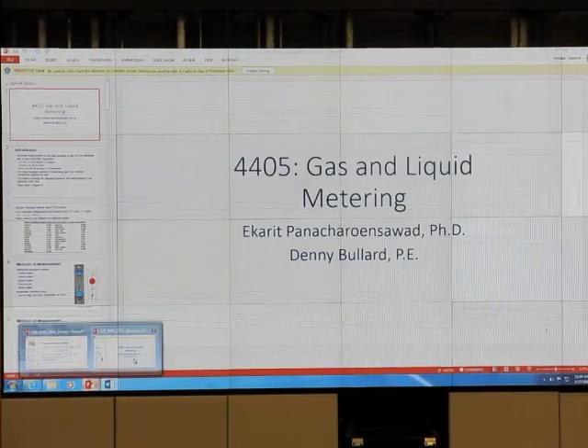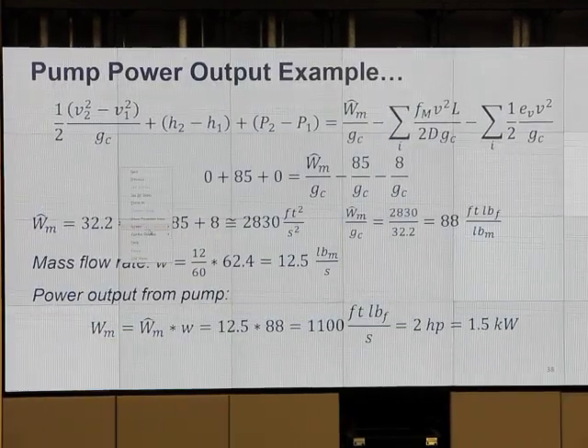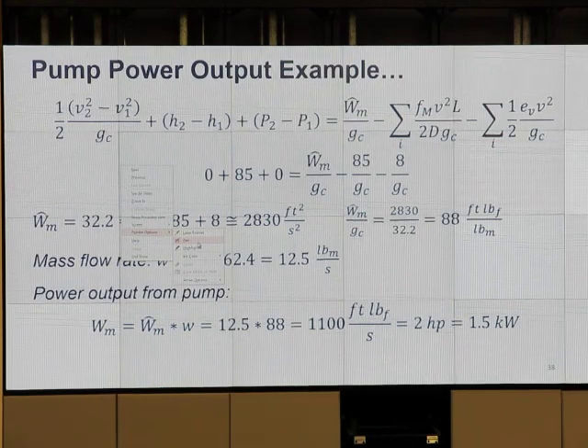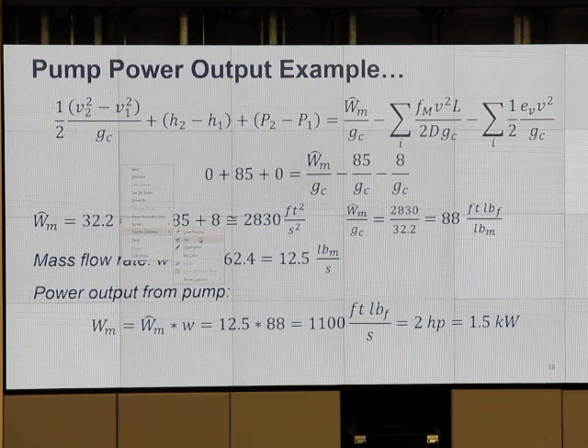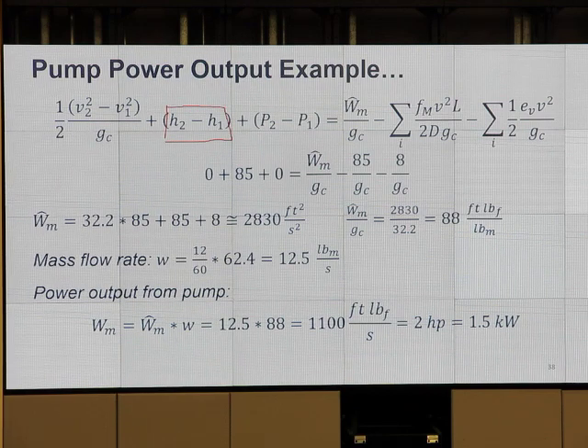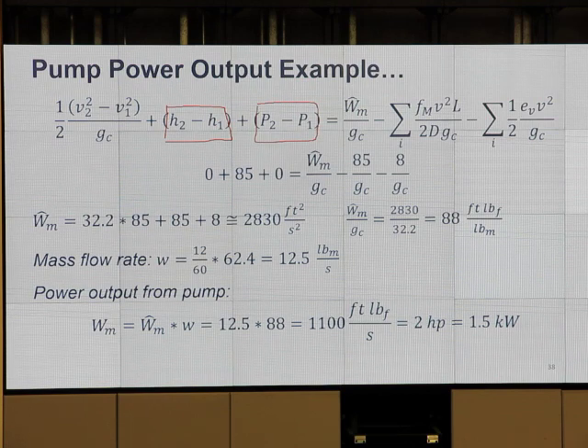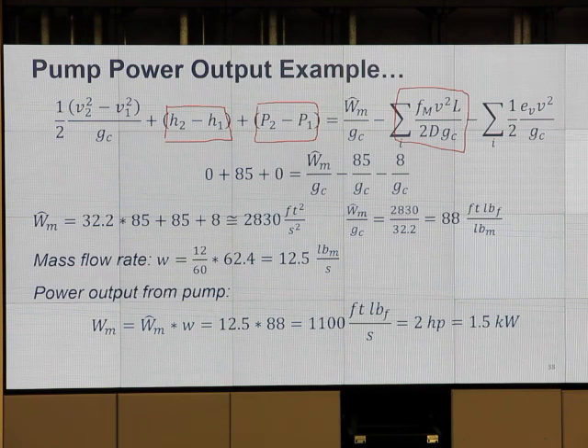Let's go back to the equation itself. If you recall, this is the equation to do the horsepower calculation — the overall mechanical energy balance. Look at this carefully. The unit of each term is feet. The unit of pressure is in feet. Everything has to be in feet; otherwise, if the units are not the same, you cannot add the terms.